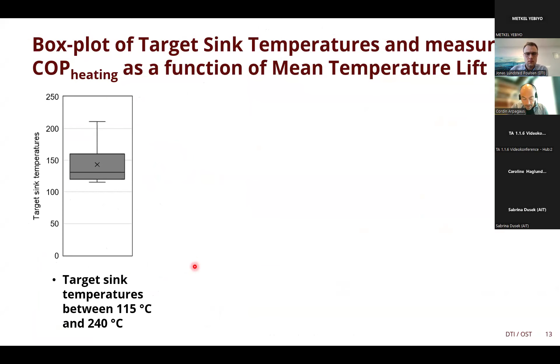So this graph shows a box plot of the target sink temperatures, which were summarized here. They are between 115 and 240 degrees. And this graph shows the heating COP as a function of the mean temperature lift. The mean temperature lift, like Jonas mentioned, is the logarithmic mean temperature between the inlet and outlet temperatures on the heat source and heat sink side. And it varies from about 26 Kelvin to 145 Kelvin in these cases.